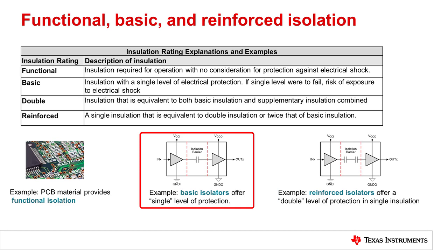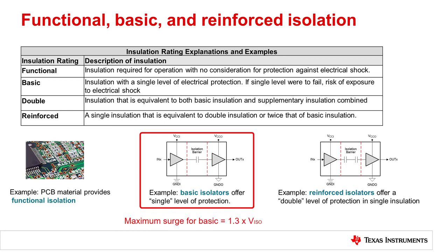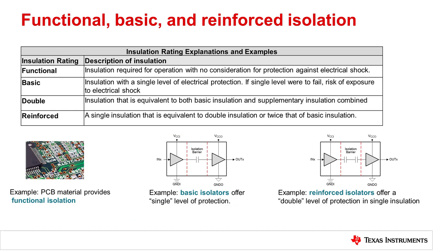Basic isolation provides a single layer of isolation protection against electrical shock as long as the insulation barrier is intact. This means that if the isolation barrier is breached, no additional barrier of protection remains. To receive the rating of a basic digital isolator with the surge test, the component must pass the surge test at 1.3 times their isolation rating. Basic isolators commonly have isolation ratings of 2.5 to 3 kV, but in some cases a basic device may have an isolation rating of up to 5 kV. High voltage systems require basic isolation to be supplemented with a secondary isolation barrier for redundancy to provide added shock protection in the event that the first barrier fails.